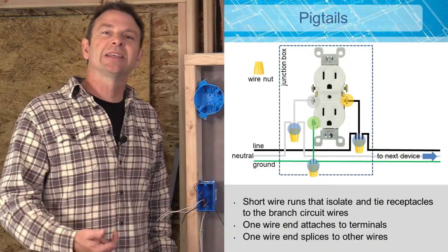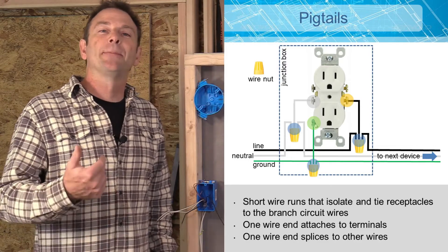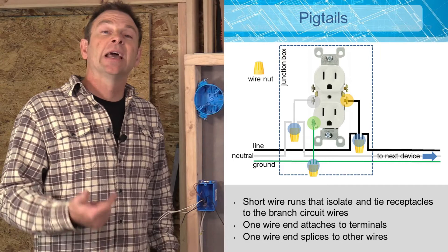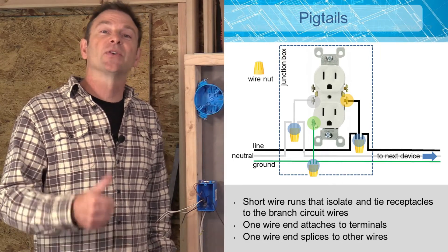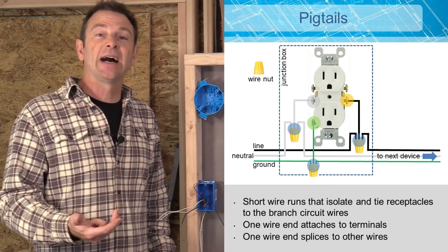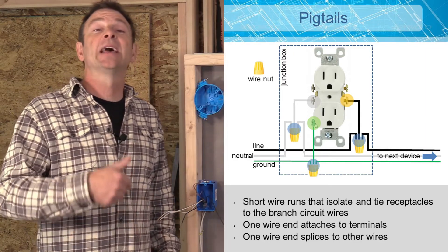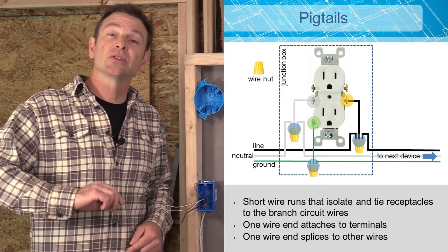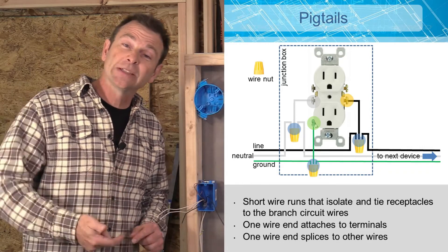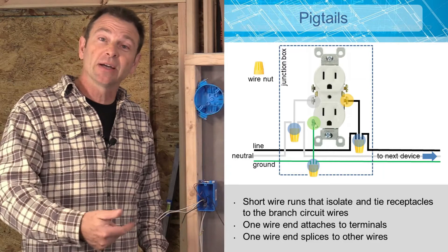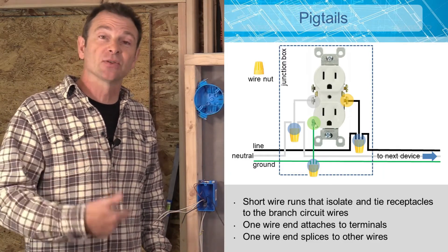On your screen, you see a schematic for a pigtail configuration for receptacle. As you see, there are short wires for your ground, neutral, and hot. And they're going to tie in with the wires that come into the box and then go out of the box. Those wires are going to get twisted all together and spliced with a wire nut. You're then going to put a hook on the end and then hook it on that single terminal.